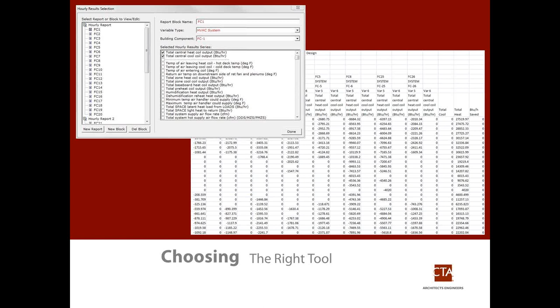Here's another example, an architectural analysis we did early in a project, trying to decide if we wanted a lot of thermal mass in our building. In general, thermal mass tends to have a flywheel effect on the heating load—your peaks aren't as big, and it delays the heat transfer a little bit. In cooling mode, this is a project in southern Nevada, in the high desert, where it gets up to about 110 degrees on our design day. The green line at the bottom is a typical wood-frame wall, with about an inch of exterior insulation and R-19. You can see the peak is pretty high, and it's maybe an hour off from the outside air temperature peak.